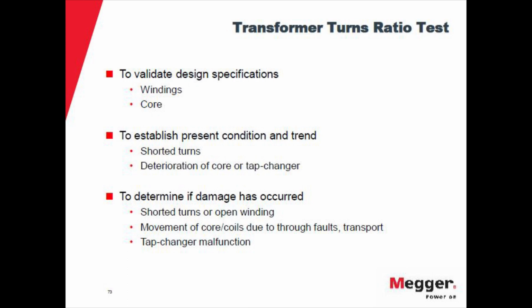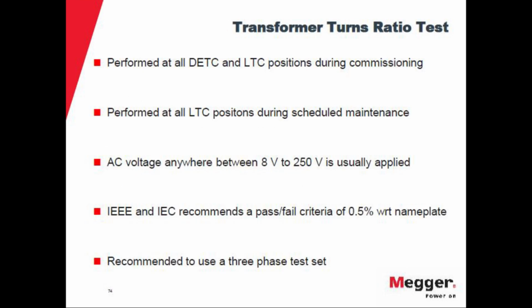After the transformer has been operating, you can determine the present condition or see if there's any change in the trend. Or after a fault or after an event, you can check if the transformer is still in operating condition or not. With the turns ratio test, you can also verify the different positions of the tap changers, if it is a de-energized or an LTC, like a load tap changer. And the test is performed usually with 8 volts to 250 volts.